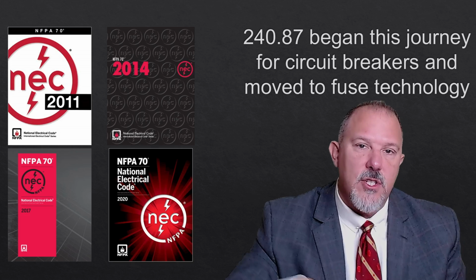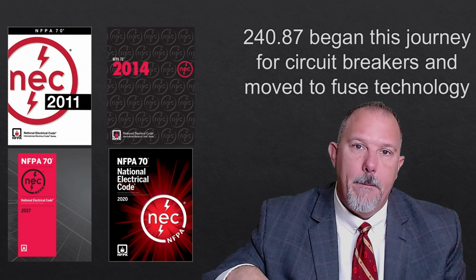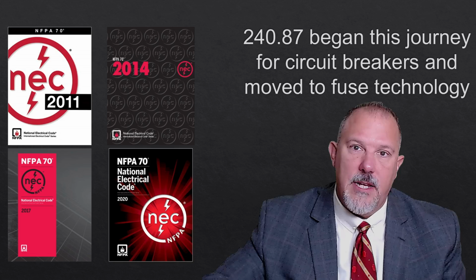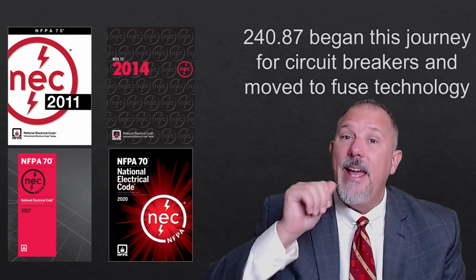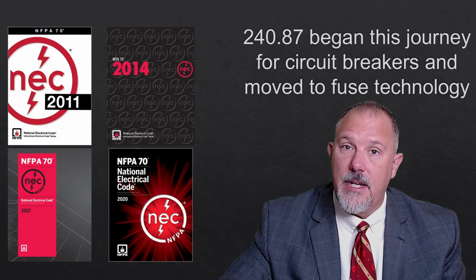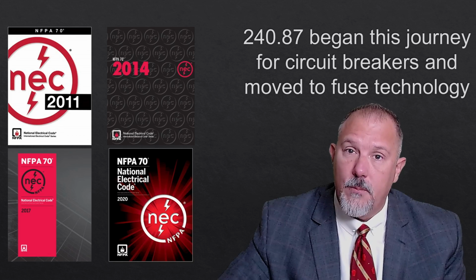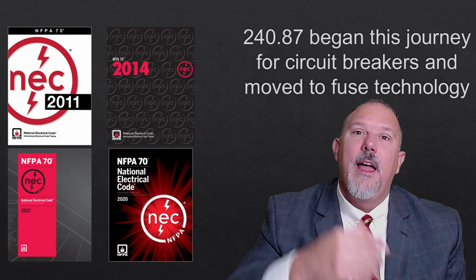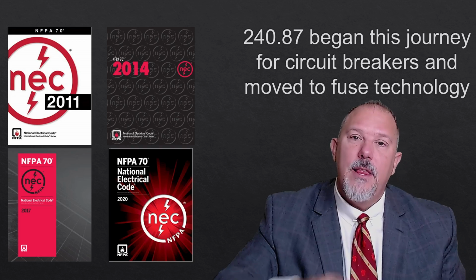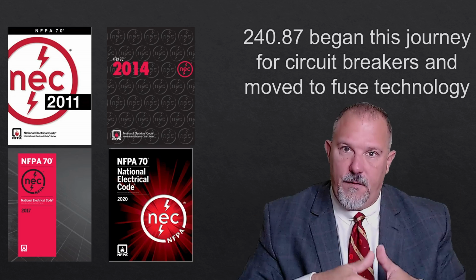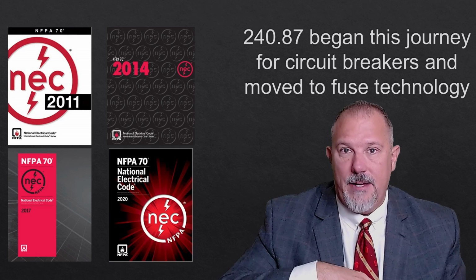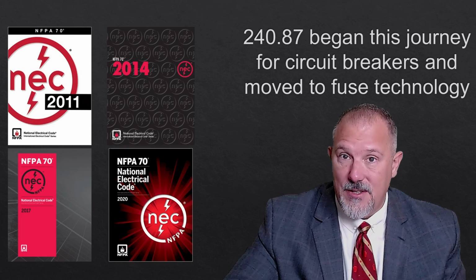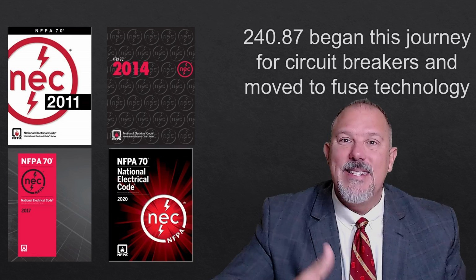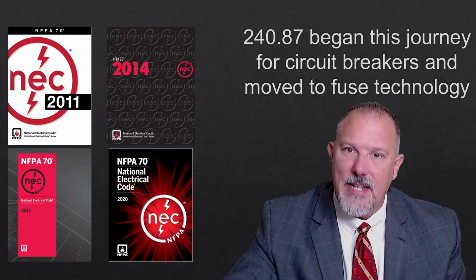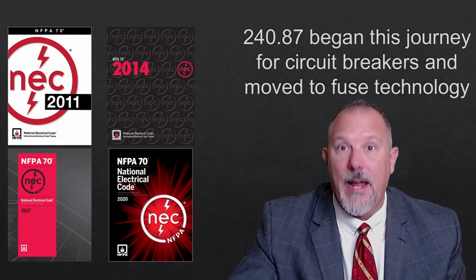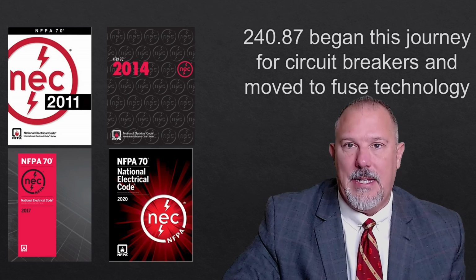So 2011 sought just for the double wides, those breakers without an instantaneous, which are only power circuit breakers, because every molded case circuit breaker has an instantaneous. Every insulated case circuit breaker is a molded case circuit breaker, and it will have an instantaneous. The instantaneous is there to protect itself, nothing else. But we leverage that to reduce incident energy sometimes. So I can still get a lot of energy on a molded case circuit breaker and an insulated case circuit breaker and a power circuit breaker that has an instantaneous.